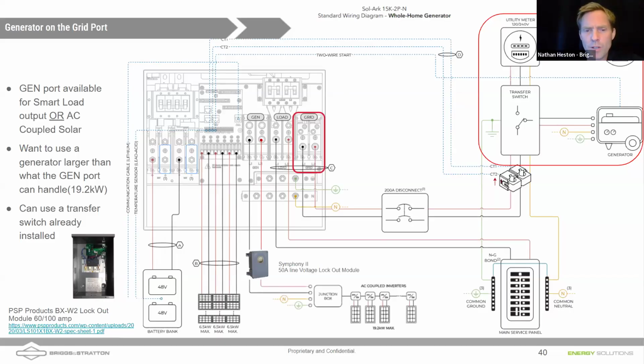Now, Daniel, what am I showing on the screen? I've got a Symphony 2 50 amp line voltage lockout module. What is that for? When the generator is running, the Sol-Ark is no longer grid forming, it's grid following. It's following the signals generated by the generator. And that kind of eliminates our ability to do what you were referring to, the frequency shifting to shut off those AC coupled solar modules.